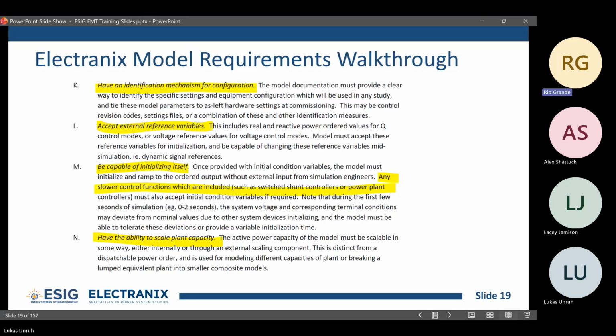You don't need to do that anymore, at least in more recent versions of these tools. You can just do ideal scaling, where at the EMT algorithm level it applies a scaling factor, and you don't need a scaling transformer or any external current injection. Most of these tools have a way to do this. I'll just show you the tool.